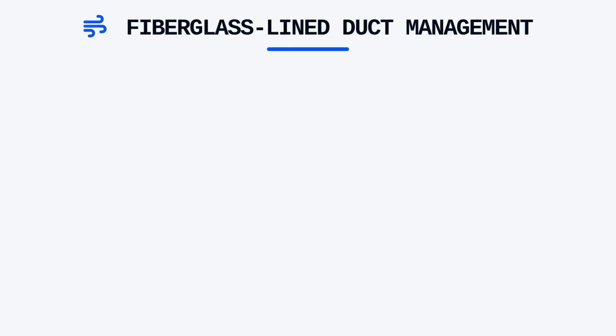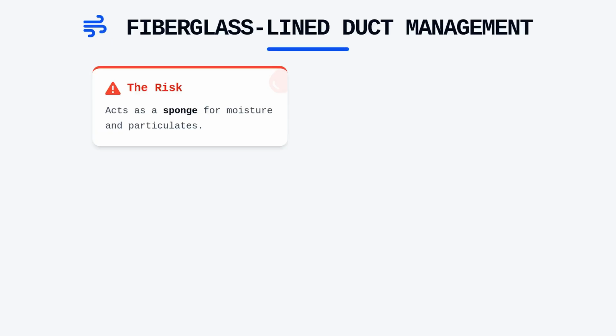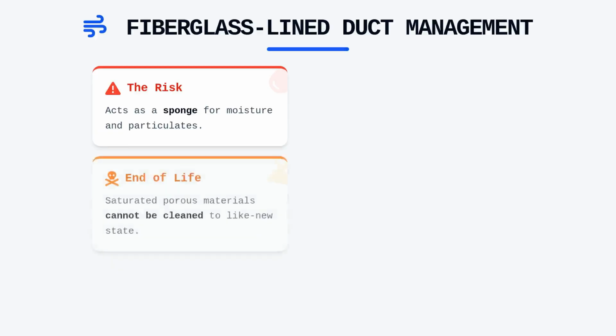Fiberglass-lined ducts present the most significant challenge in the field because the insulation material often acts as a sponge for particulates and moisture. When you encounter a lining that has been compromised by moisture, you are essentially looking at an item that has reached its end of life, as porous materials do not clean to a like-new state once saturated.